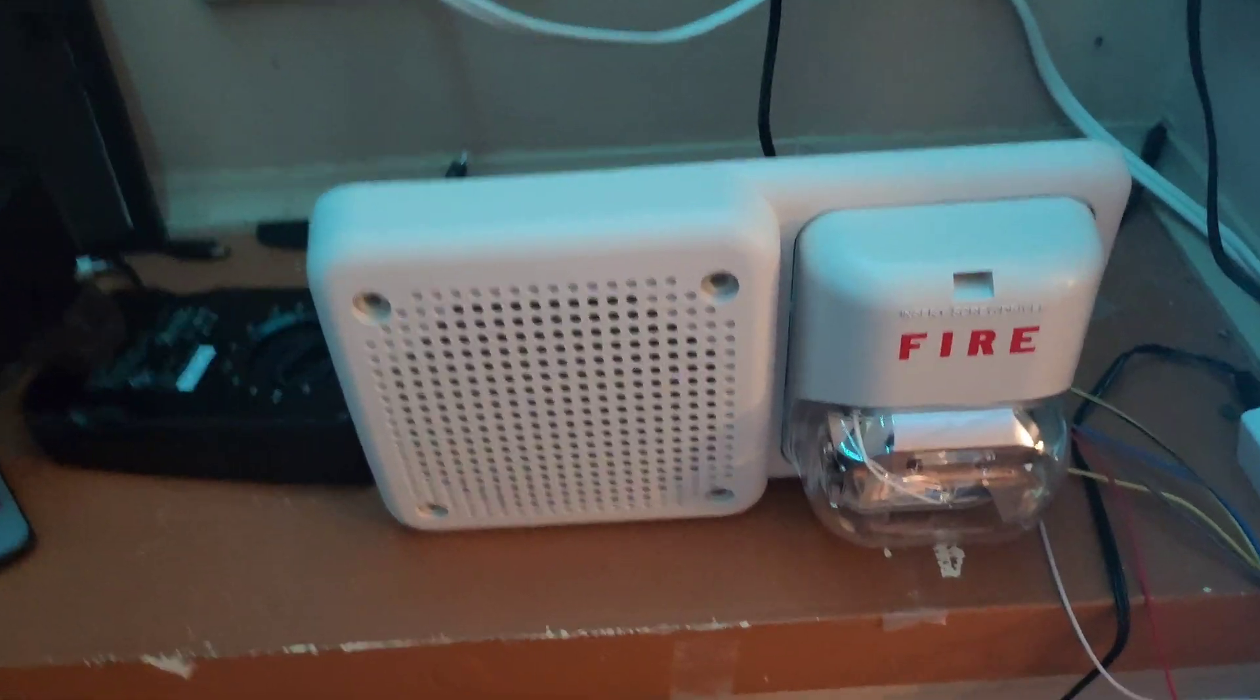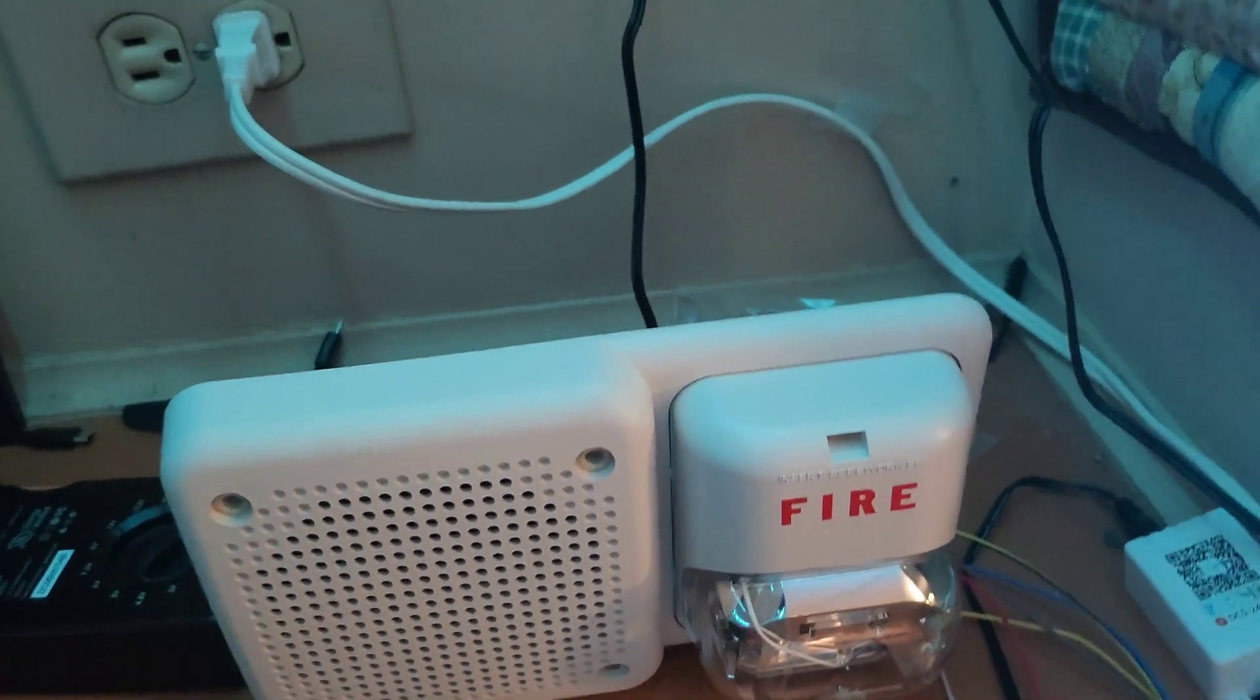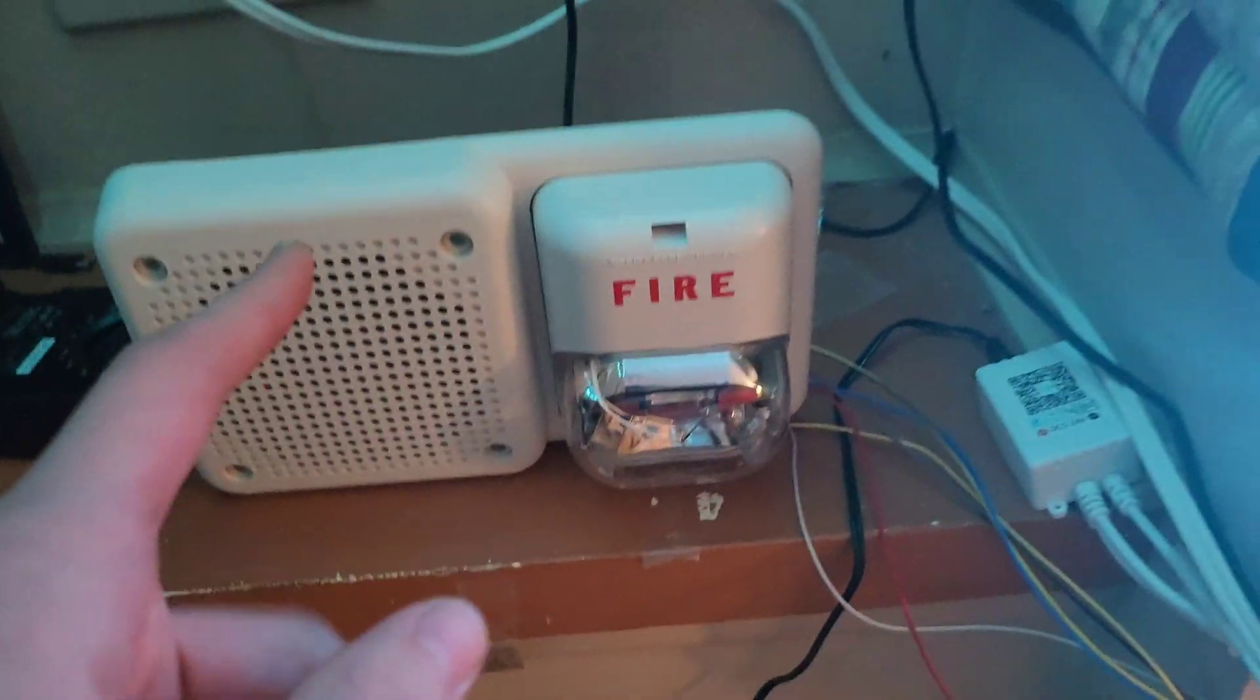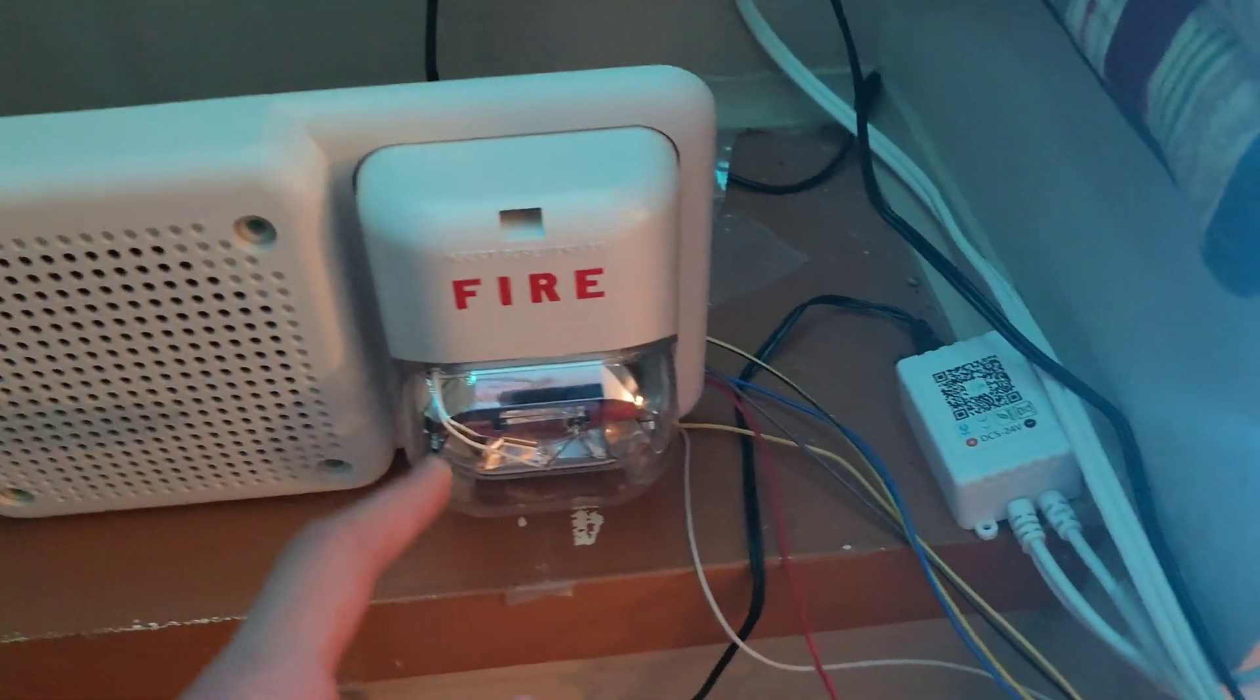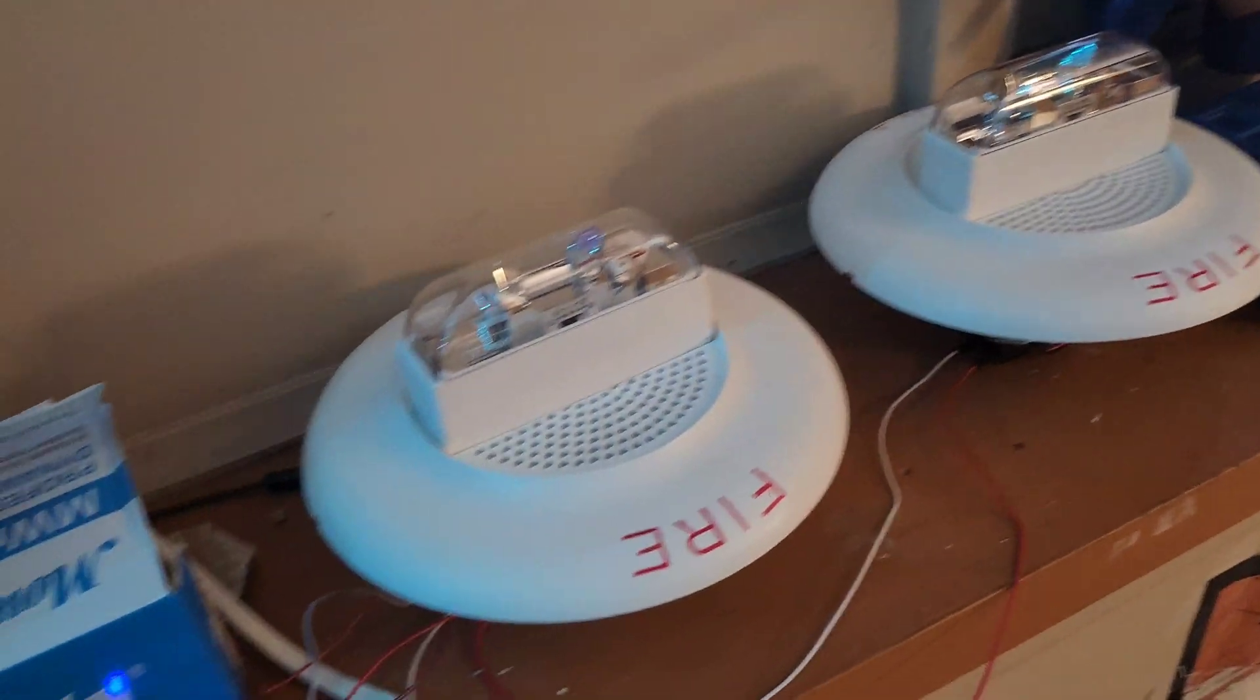So here we have the classic speaker strobe. Now for all my speaker strobes, the speakers will not be playing any message. And this one is at 110 candela. However, there's an issue with this because I made my own synchronization thing, which you'll see later. When it's on my synchronization thing, this one will not flash the full 110 candela, which I've noticed. So that's a little odd. And these two over here will be flashing at 95 candela.